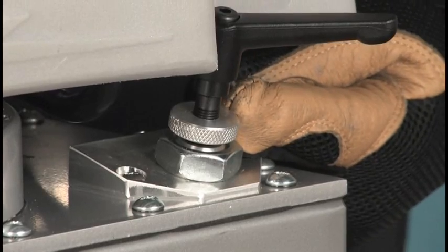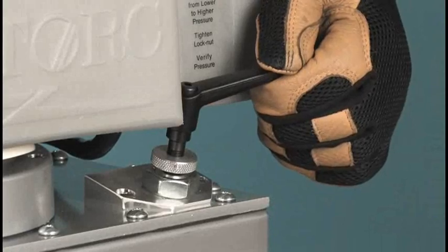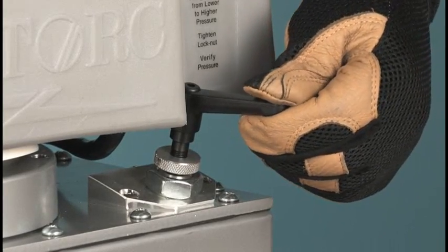Note that there is a locking nut under the regulator knob to keep it from vibrating loose. By limiting the pressure the pump will generate, we control the maximum torque output of the wrench.